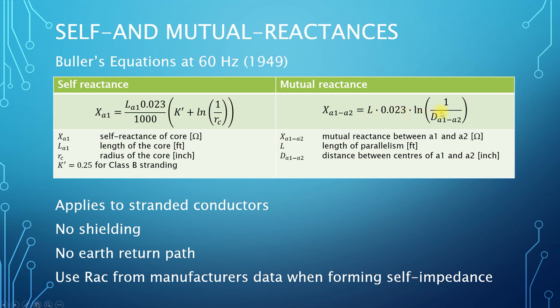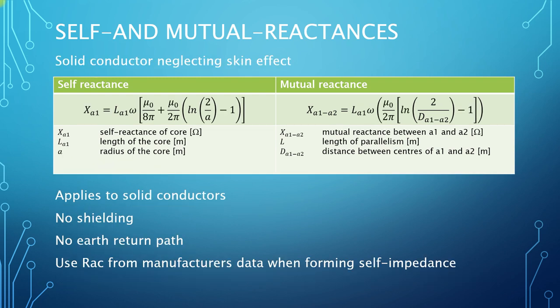The K-dash term effectively takes account of the internal inductance of the conductor — that associated with the magnetic field internal to the conductor — while the logarithm term is associated with the magnetic field external to the conductor. The mutual reactance is calculated in a similar way, and the key issue here is the distance between the conductors: the larger the distance, the smaller the mutual reactance. An alternative formulation is to consider the conductors as solid conductors and, if we neglect skin effect, the following equations can be derived.